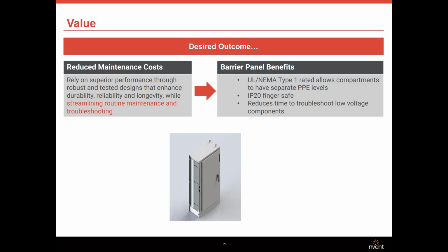So with the UL Type 1 rated enclosure, we have UL Type 1 rated compartments requiring separate PPE levels. And we all know that the lower the level of PPE that's required, the more likely the maintenance guys are to wear it. These are also going to be IP20 finger safe.